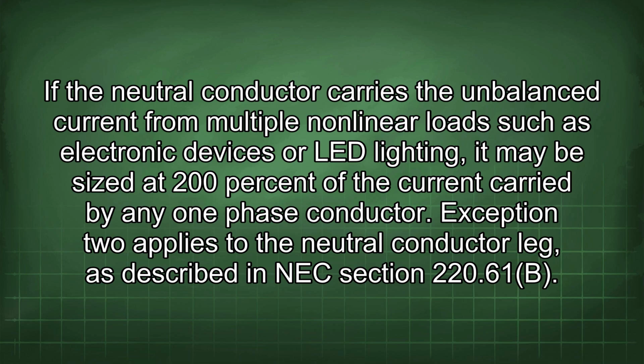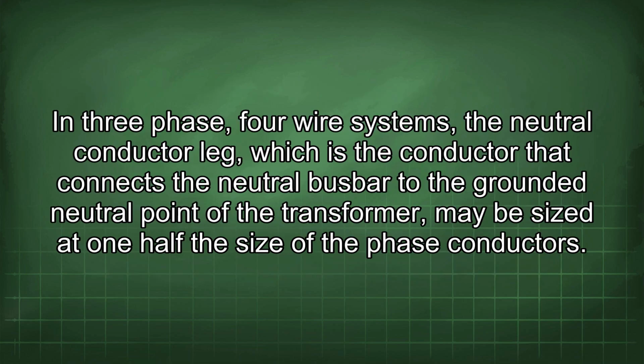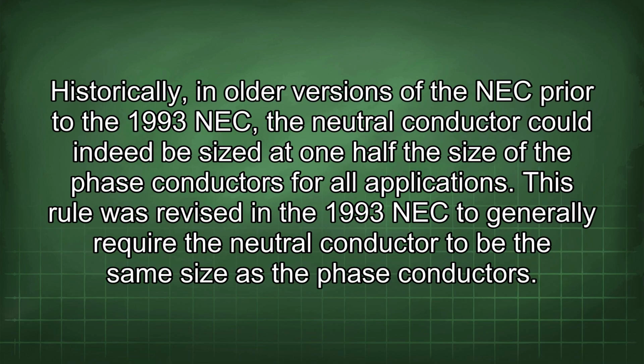Exception 2 applies to the neutral conductor leg, as described in NEC section 220.61(B). In three-phase, four-wire systems, the neutral conductor leg, which is the conductor that connects the neutral busbar to the grounded neutral point of the transformer, may be sized at 1/2 the size of the phase conductors. Historically, in older versions of the NEC prior to the 1993 NEC, the neutral conductor could indeed be sized at 1/2 the size of the phase conductors for all applications.